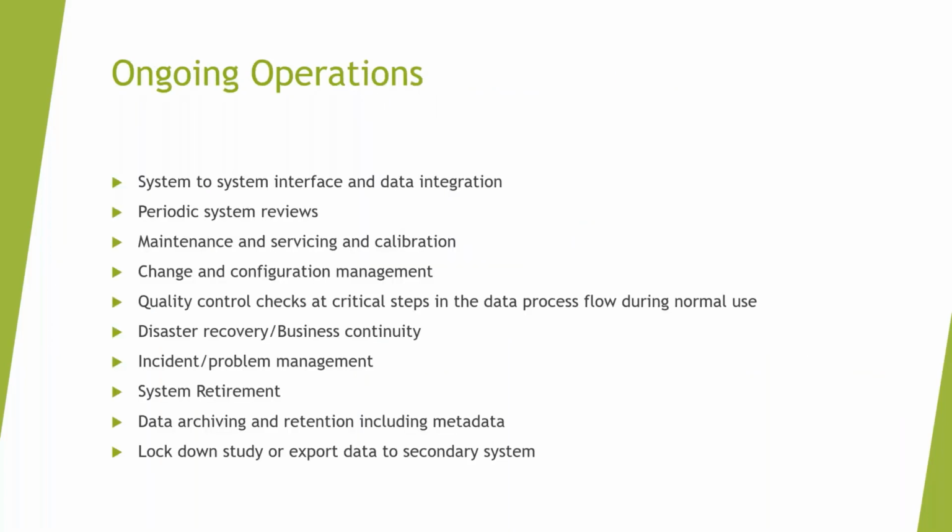Ongoing operations. Once the system is live, there should be lots of ongoing operations which continue. And as auditors, we think about what elements are defined, implemented and controlled, specifically to assure data integrity. So items such as: what system-to-system interface and data integration is there? Are there appropriate built-in checks for the correct and secure entry and processing of the data? What periodic system reviews are conducted? What do they review, how often, and has it been done? What maintenance, servicing and calibration activities are conducted? Who performs these and at what frequency, and does it comply with validated requirements, etc.?